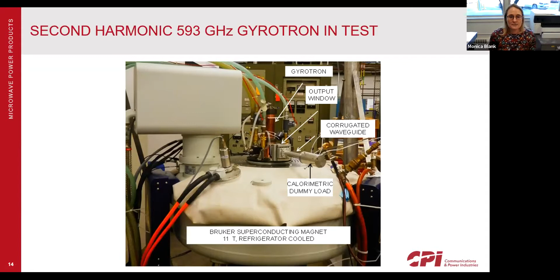We do use the second harmonic with all of our family, the Bruker CPI family of gyrotrons. So if you're doing the math in your head, that would be like a 22 Tesla magnet for 593, at 28 gigahertz per Tesla, but we're using second harmonic. So Bruker made an 11 Tesla superconducting magnet that's refrigerator cooled. The gyrotron is sitting in here. It's kind of hard to see in that big, huge magnet, but it's there. The collector's up top, and these are the cooling inputs. The window is back here, and for all the gyrotrons, we have a not permanently attached, but mostly permanently attached little unit that houses one piece of waveguide that makes it very easy for Bruker installers to connect the transmission line. So that's the gyrotron in test.